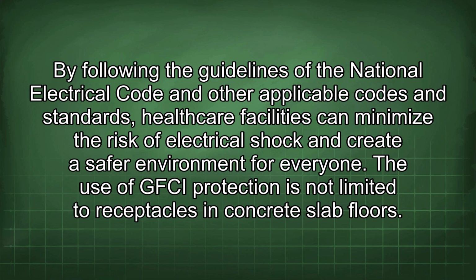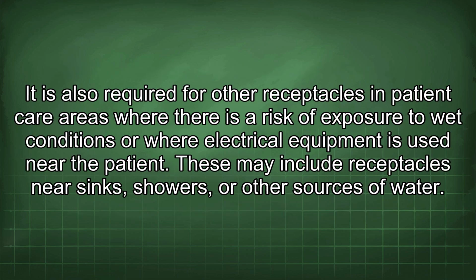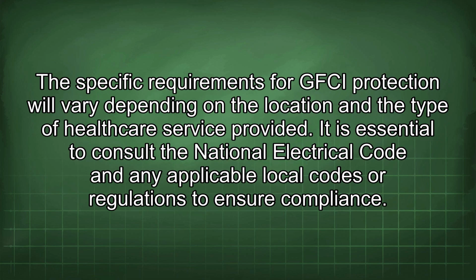The use of GFCI protection is not limited to receptacles in concrete slab floors. It is also required for other receptacles in patient care areas where there is a risk of exposure to wet conditions or where electrical equipment is used near the patient. These may include receptacles near sinks, showers, or other sources of water. The specific requirements for GFCI protection will vary depending on the location and the type of healthcare service provided. It is essential to consult the National Electrical Code and any applicable local codes or regulations to ensure compliance.